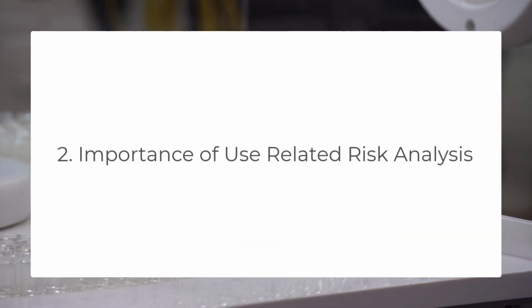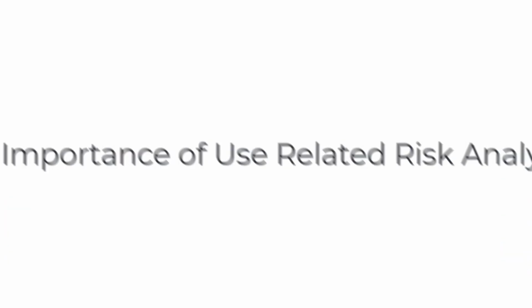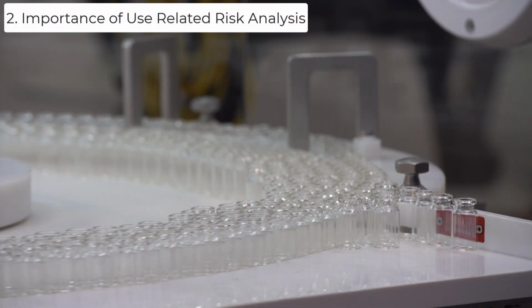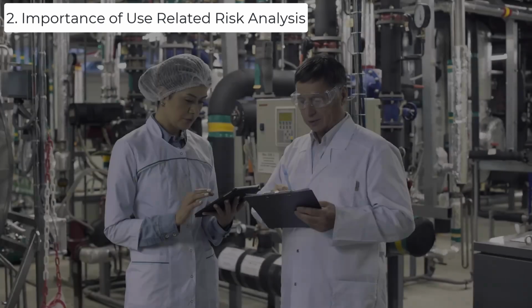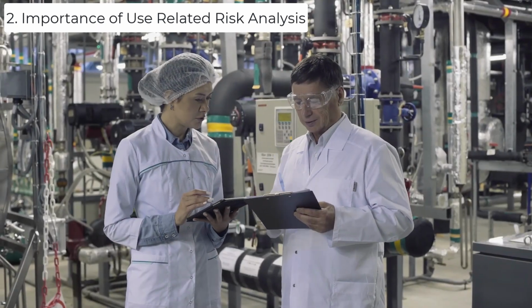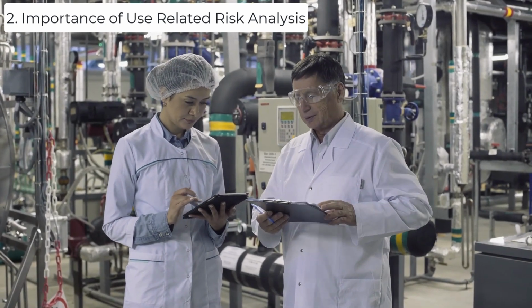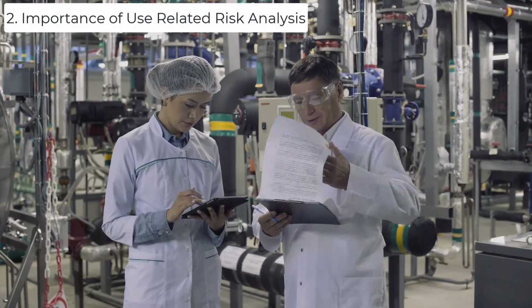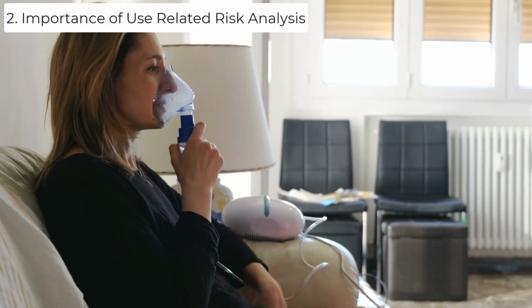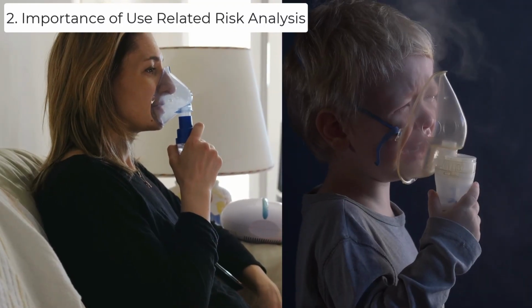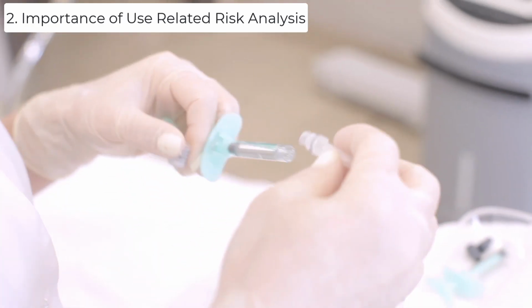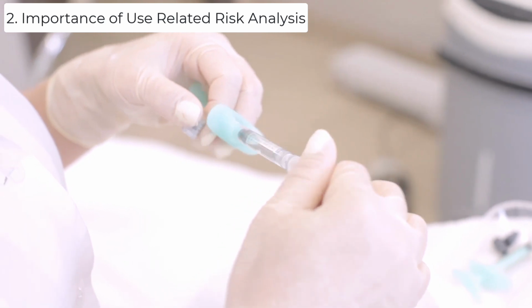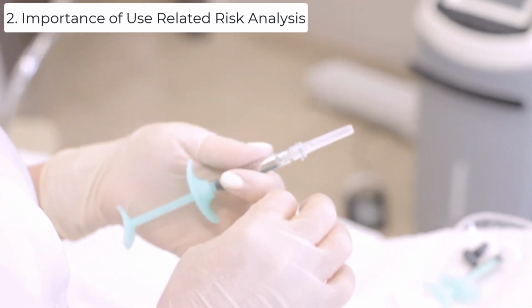Topic 2. The importance of the use-related risk analysis. Like all medical devices, combination products are subject to design validation and use-related risk analysis where appropriate. A use-related risk analysis is a subset of the overall engineering risk analysis, with focus on intended use and risk of foreseeable misuse. The use-related risk analysis should consider all potential risks associated with the combination product as a whole, not just the device, the drug, or the biological product alone.